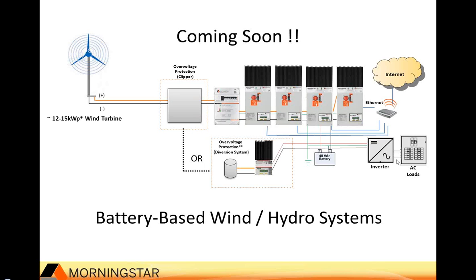Question about the DC transfer switch. Again, this product is still being finalized in development, but essentially what it will be is a DC transfer switch that will accept up to a 600 volt input, and it would allow the automatic transfer of the PV array from the grid tie inverter to our 600 volt charge controller during a power failure. So an existing grid tie system that is pre-wired and already completed could have a 600 volt charge controller added to it after the fact. You would not have to reconfigure the array at all. The transfer switch, when the power fails, would throw the array over to the charge controller and allow you to charge a 48 volt battery. So you are given some power in an off-grid way when there's an outage.